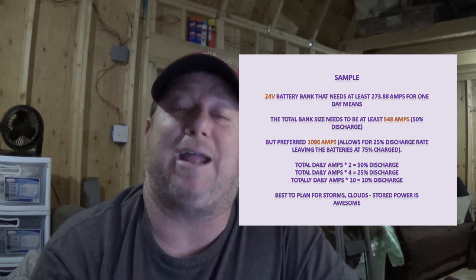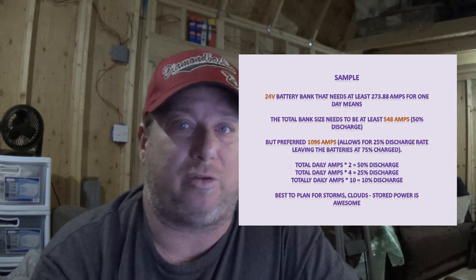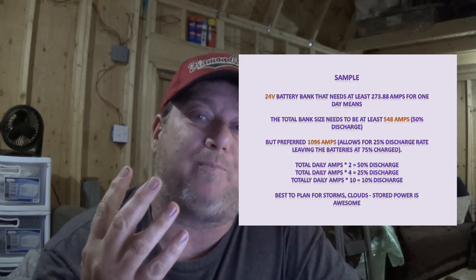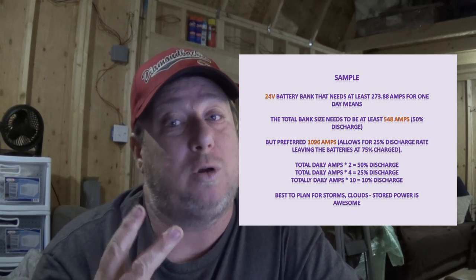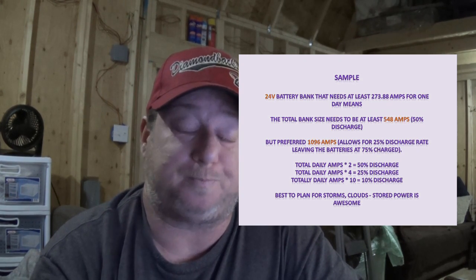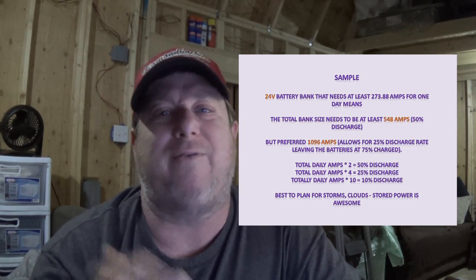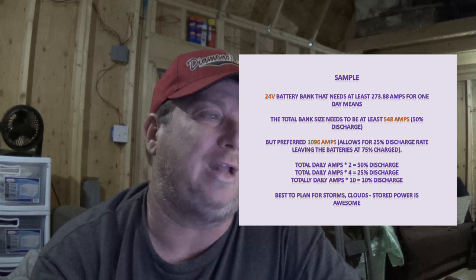So now, how do I figure that out? What you're going to do is take the 273.88 amps that I need for the day, and I'm actually going to multiply that by 4. Multiplying it by 4 will give me a 25% discharge rate. If I multiply it by 2, it will give me a 50% discharge rate. So we're going to go 4. And I think the number came out 1,095 and some decimal. I just rounded it to 1,096. So for my 24 volt battery bank, I need at least 1,096 amps in that 24 volts.